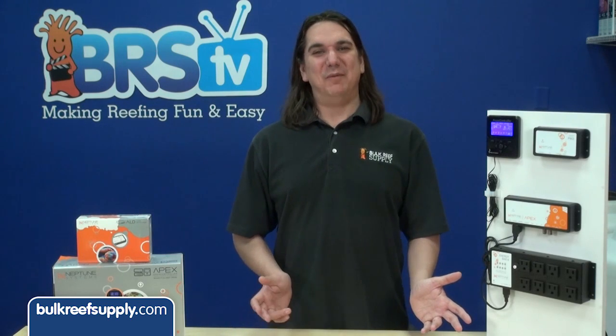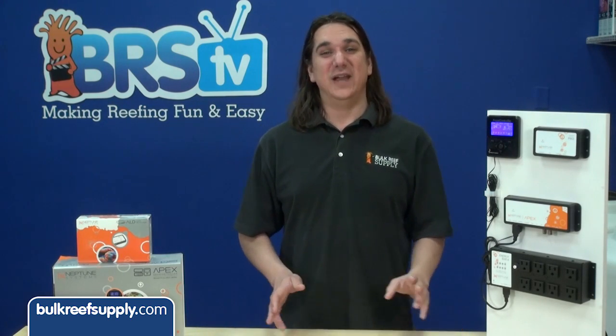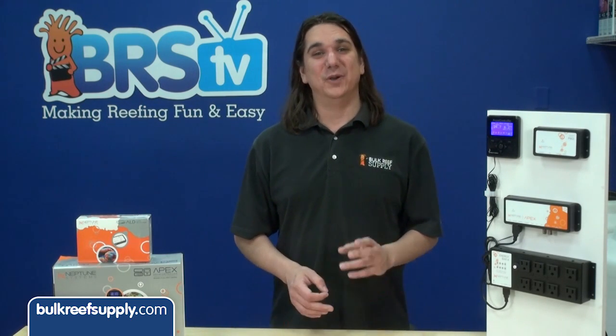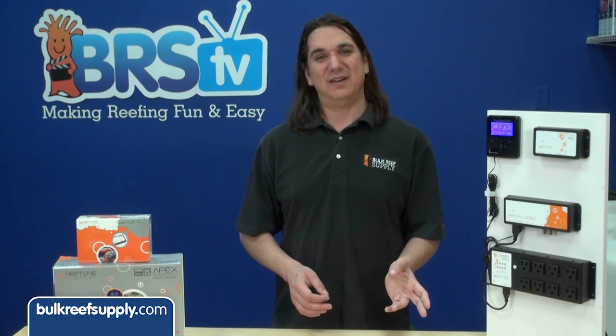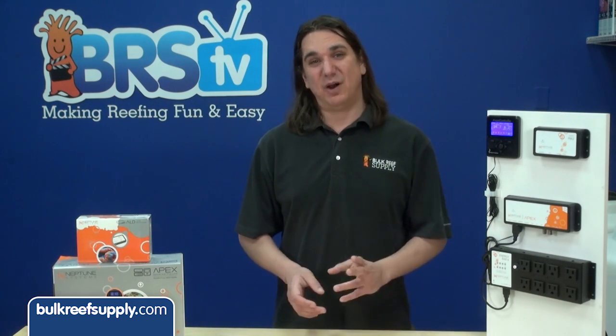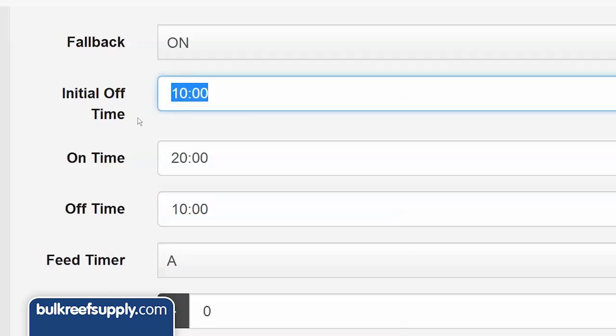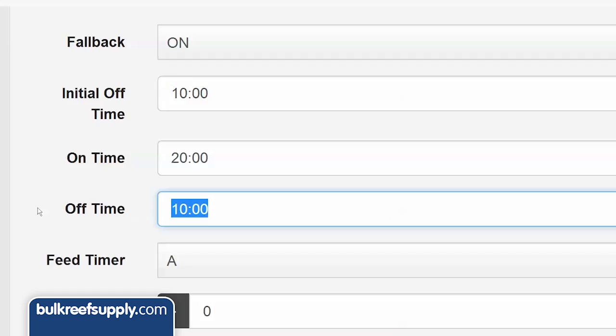This is probably the most commonly misunderstood portion because the way it is displayed implies that a 10-minute initial off time only applies to the start of the initial cycle, when in fact it is part of every cycle. This means if we enter 10 for the initial off and 10 for the off time, what we would really get is 10 plus 10, resulting in 20-minute off cycles.